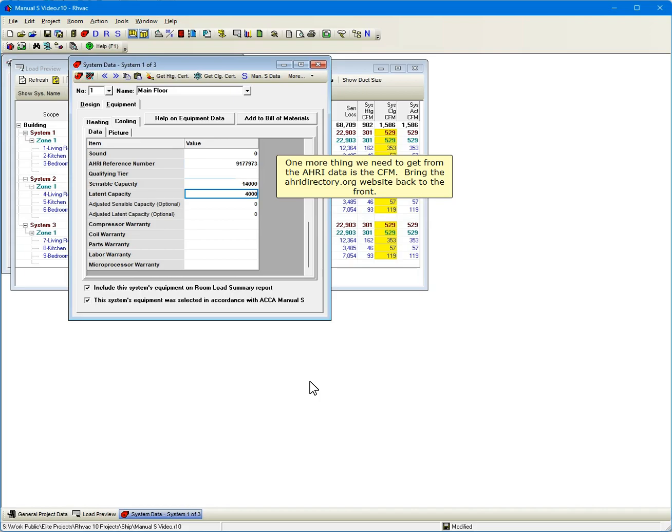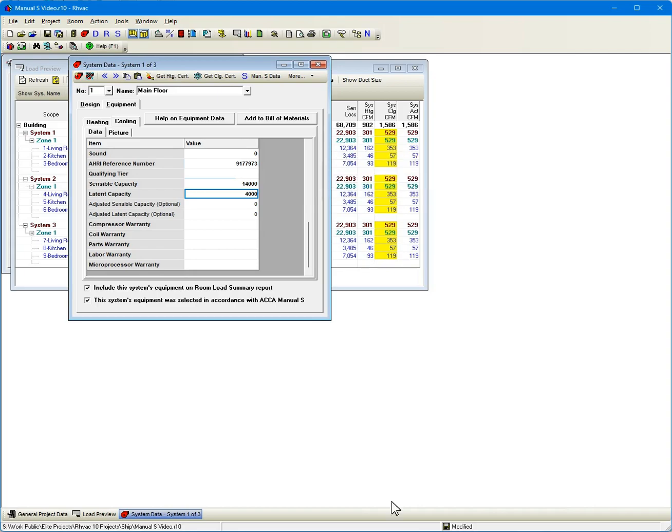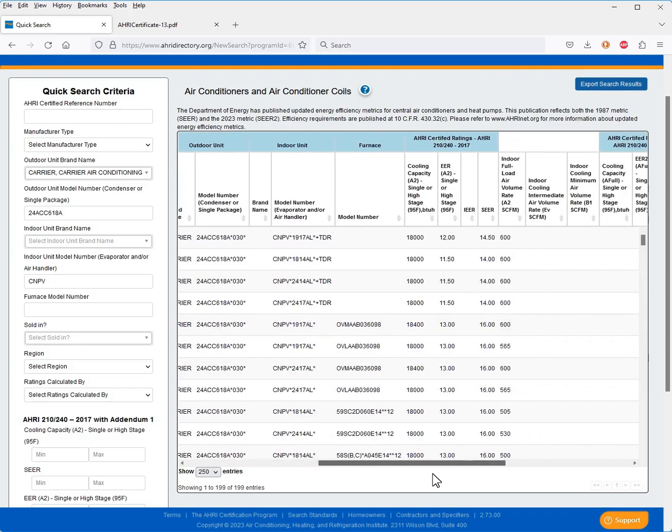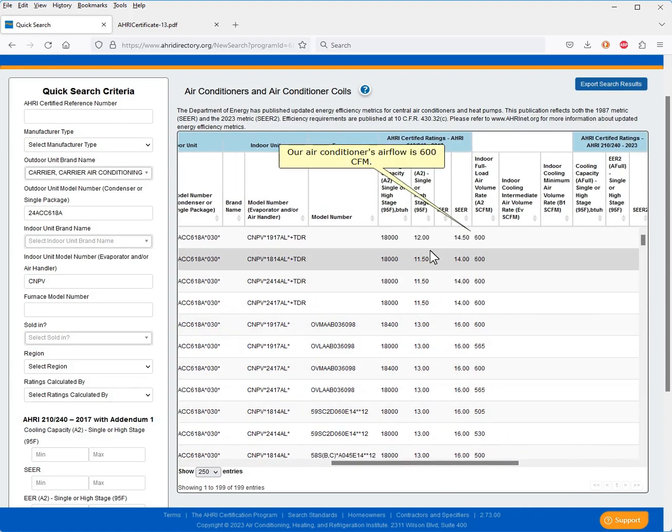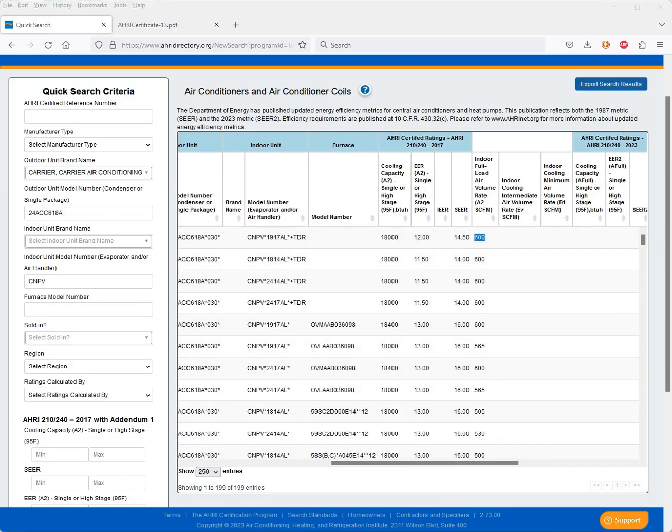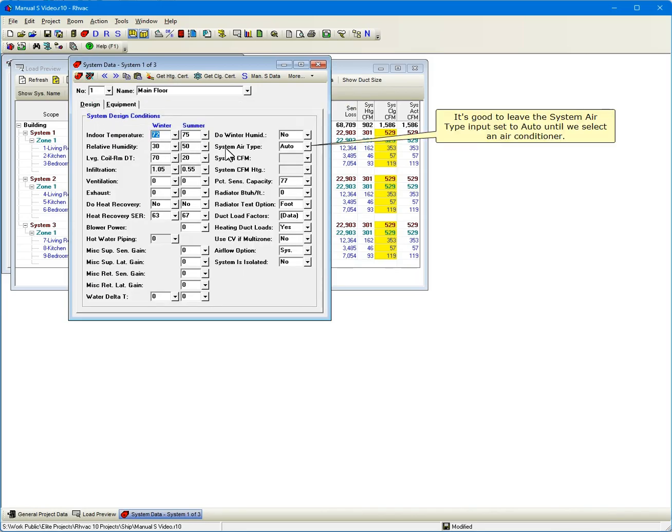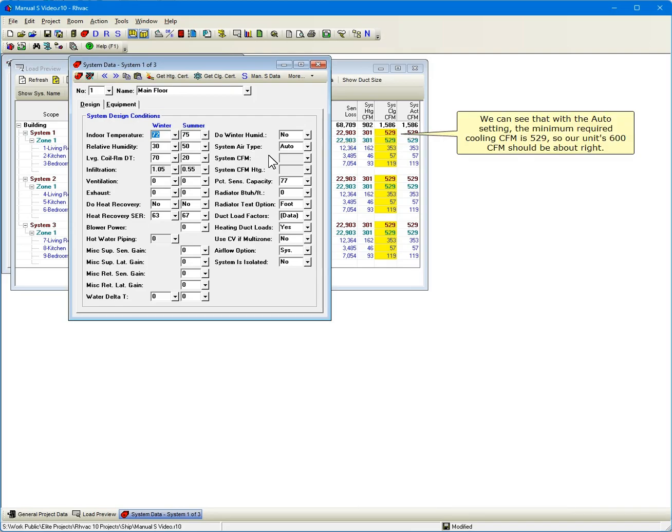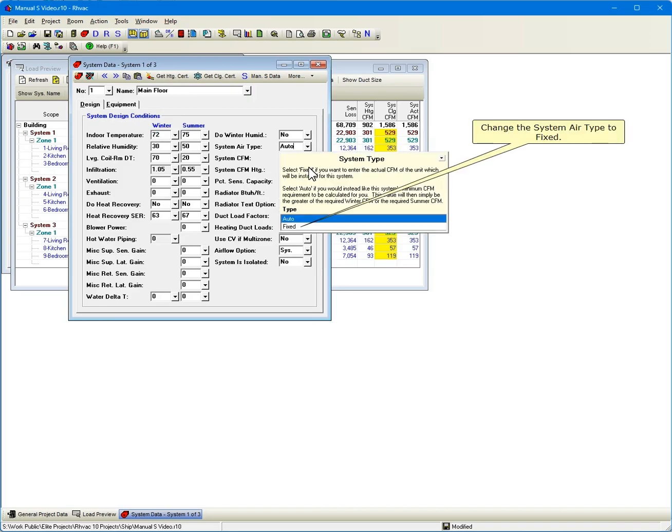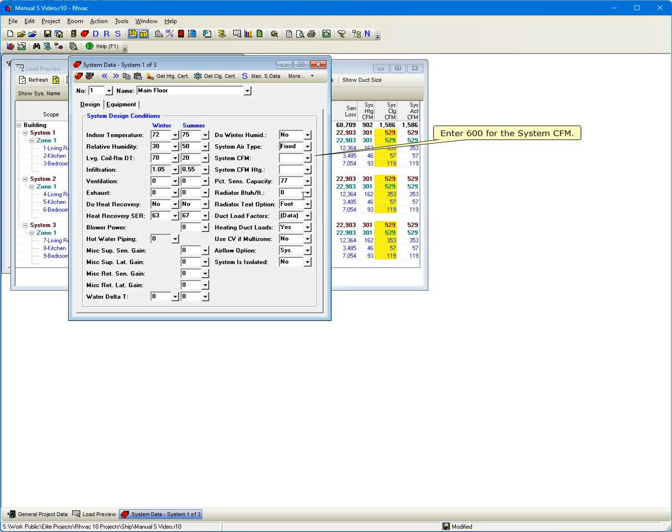One more thing we need to get from the AHRI data is the CFM. Bring the AHRIDirectory.org website back to the front. Our air conditioner's airflow is 600 CFM. Click the Design tab. It's good to leave the System Air Type input set to Auto until we select an air conditioner. We can see that with the Auto setting, the minimum required cooling CFM is 529, so our unit's 600 CFM should be about right. Change the System Air Type to Fixed. Enter 600 for the System CFM.